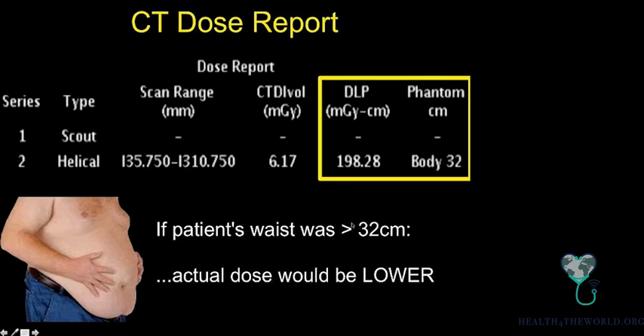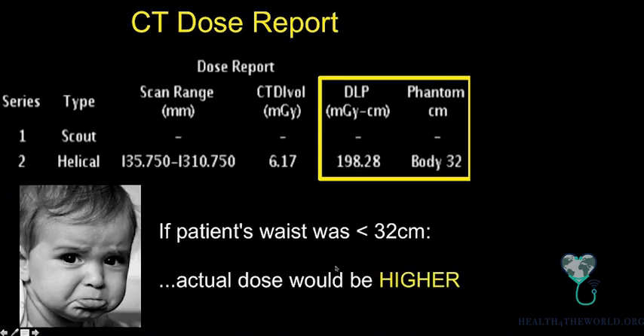What if the patient is actually bigger than 32 centimeters? Think of it like food coloring in water — the same dose delivered to a larger body area is more dilute, so actual dose is lower. Conversely, if the patient is a baby and definitely not 32 cm in diameter, you're giving the same amount of dose to a smaller body, meaning higher concentration. Depending on whether the phantom was entered correctly and whether the patient matches the phantom size, reported doses can be higher or lower than reality. This is an estimate, not a measurement.